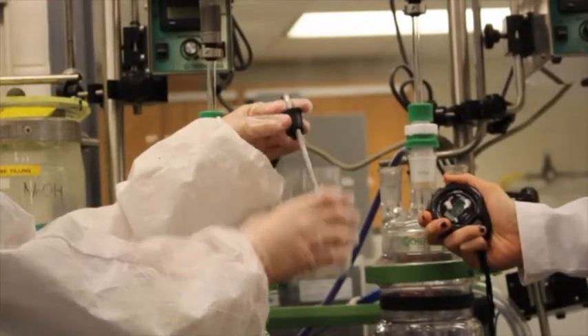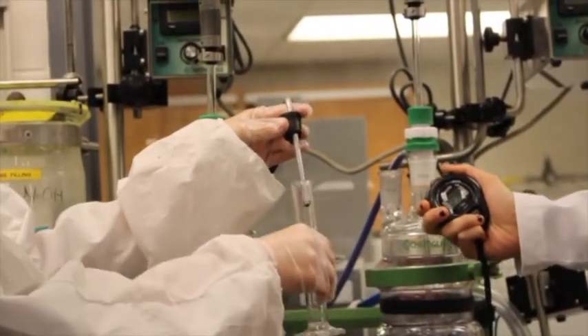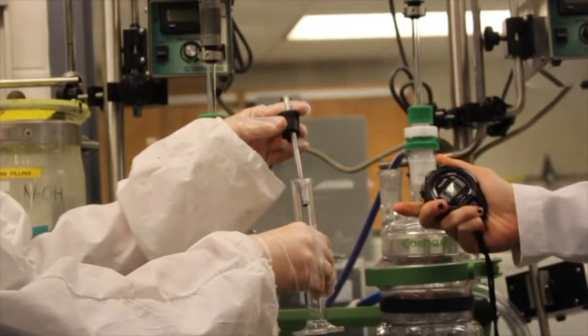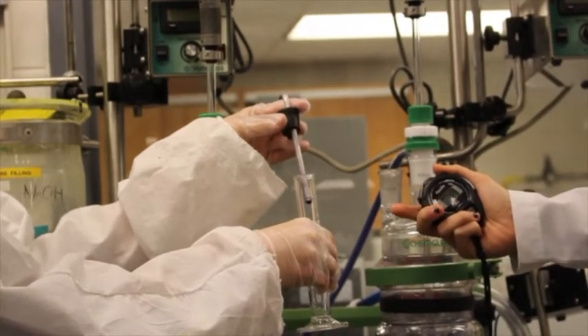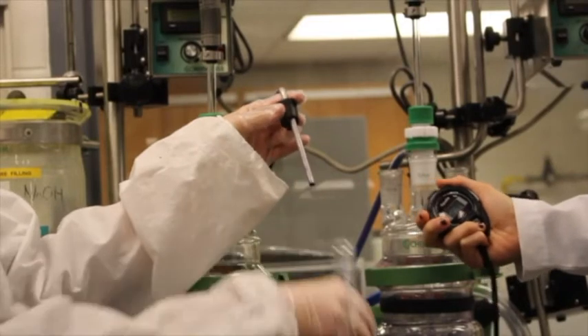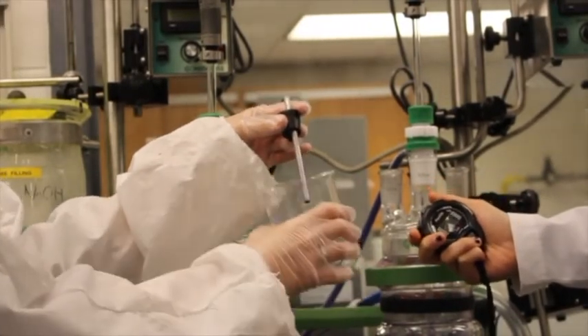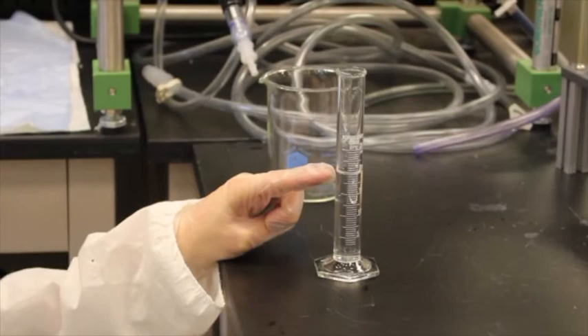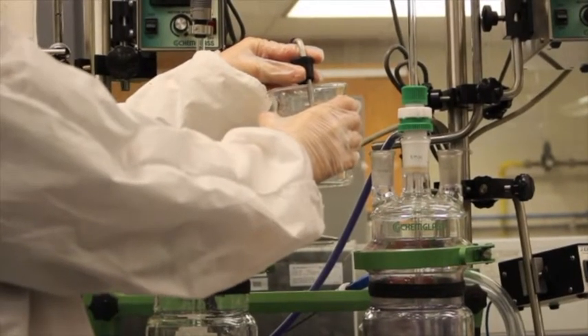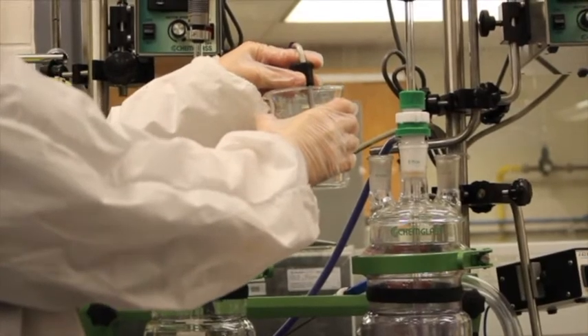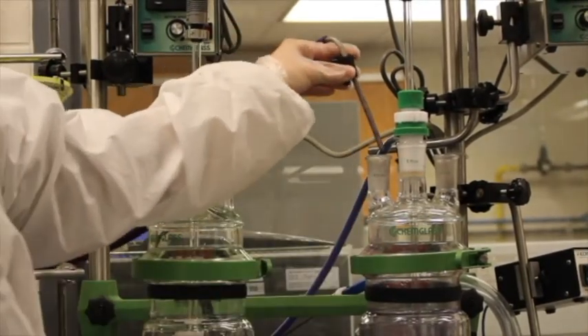Move the line from the waste beaker to the graduated cylinder and begin timing. Stop timing and remove the tube from the graduated cylinder simultaneously and place it back into the waste beaker. Measure the volume of the collected water to obtain a volumetric flow rate. After the calibration procedure is finished, make sure to put the tube back into the reactor.